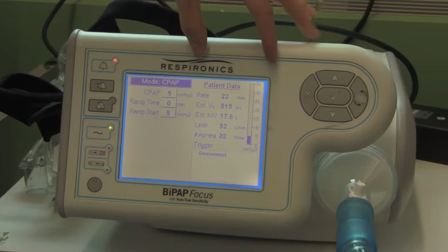This column here is what the machine's set at and shouldn't change. This is the patient data and is telling you what happens each time the patient takes a breath. There's the respiratory rate, the tidal volume, the minute volume, and this bit here is called leak, which will be discussed further in the mask fitting. This apnea is if the patient stops breathing for any length of time, the machine will alarm.